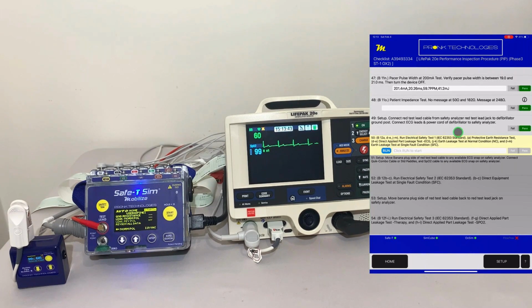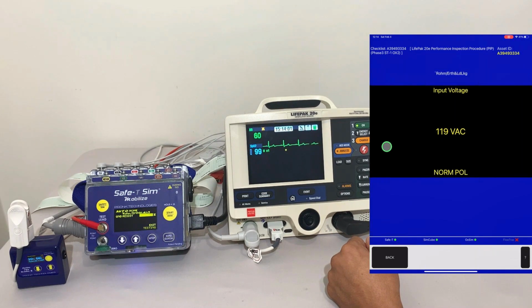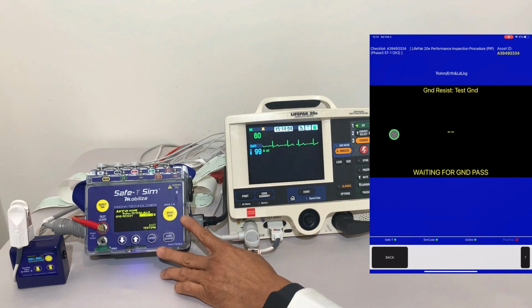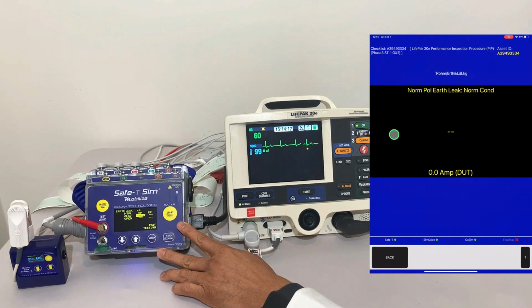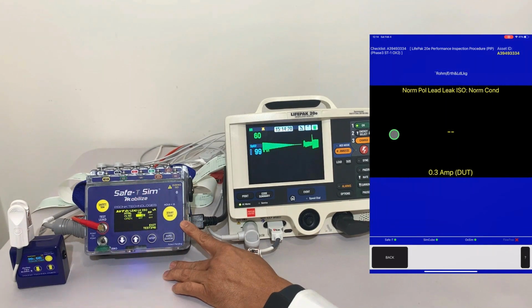So in this case, we're going to be doing a number of different tests simultaneously. We're going to do the protective earth resistance test, a direct applied parts leakage test, and we're also going to do an earth leakage test, all automated using the safety analyzer. So we simply tap on the run button here, and the Mobilize app will instruct the safety analyzer to go ahead and begin that series of tests. So it's already programmed to know what tests we need to do. It knows the standard limits for the 62353 and what the pass-fail limits are that we need to comply to. So it's going to go ahead and execute those required tests.